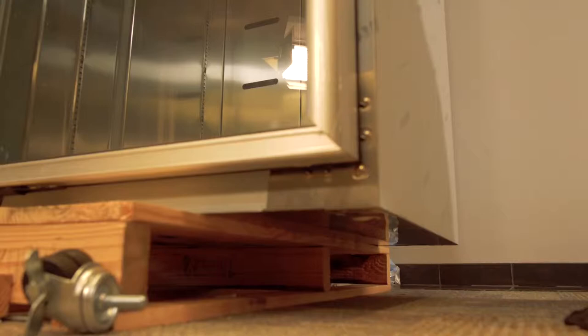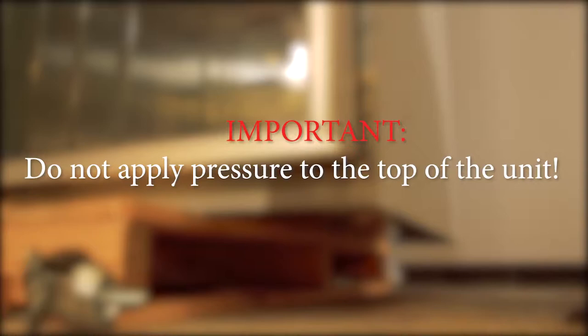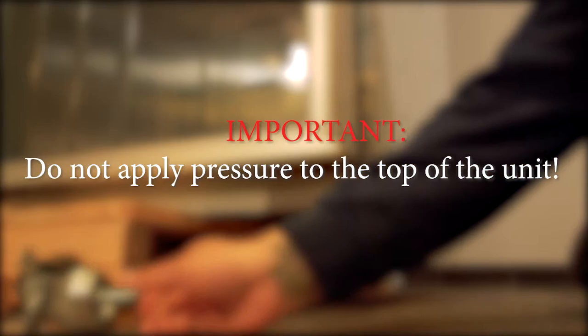Gently guide one side of the refrigerator to the edge of the pallet so the caster holes can be accessed. Do not apply pressure to the top of the unit during the installation or damage to the refrigeration components will occur.